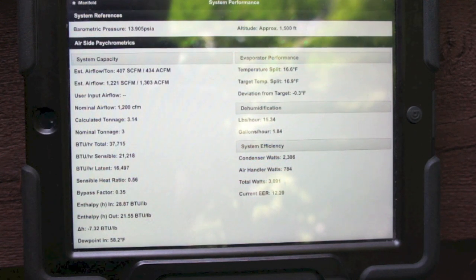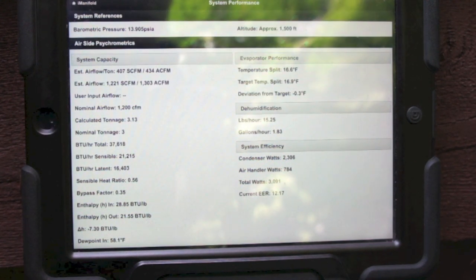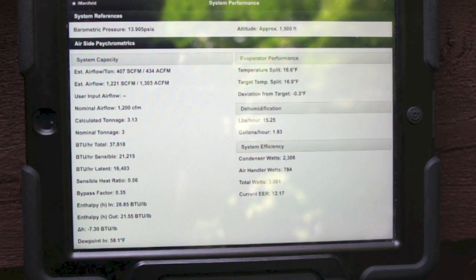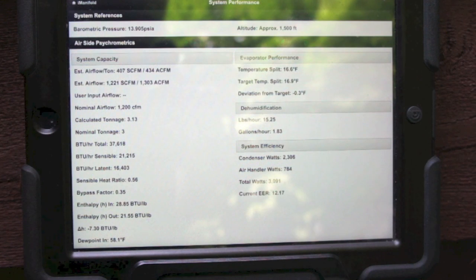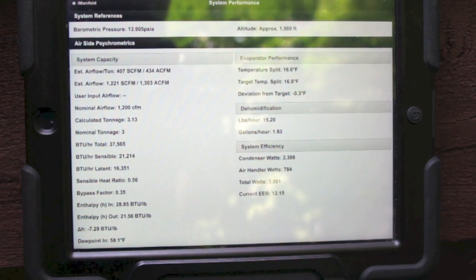Traveling across the country, I've had my lunch handed to me more than once trying to measure airflow simply because the system was not conducive to it, especially when we got into flex duct systems and other systems that just simply you could not measure airflow easily. So this is by far the fastest, easiest way. It's corrected. Let's go ahead, we'll take a look at my thermostat inside, we'll see what my thermostat airflow estimates and look at it compared to what we have the iManifold calculating.